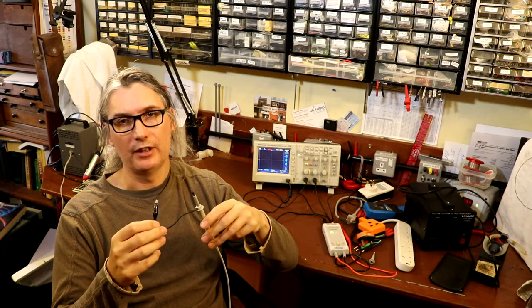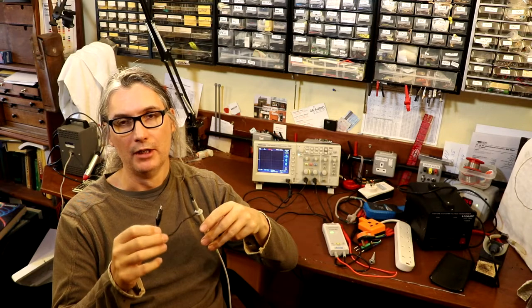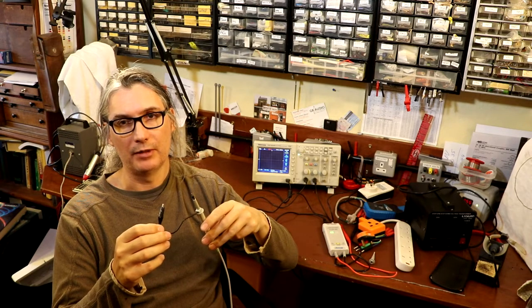Having established that it really is a pretty bad idea to connect the ground of our scope to either the live or neutral of our main supply, how do we make our measurement? Well, the first method people used to employ, which was really stupid and very dangerous, was to actually disconnect the earth wire from the oscilloscope to remove its ground reference, and then clip the ground connector of the scope probe onto the neutral side of the mains. I say that's a non-prescribed method — it's really dangerous and stupid, because if you get it wrong, the body of your oscilloscope becomes live.